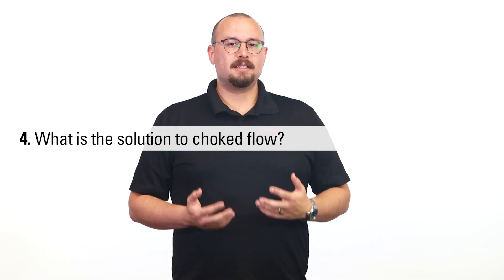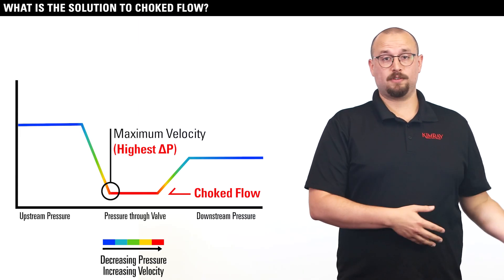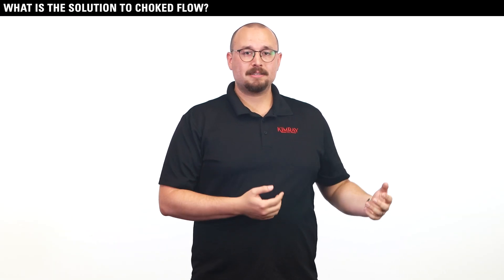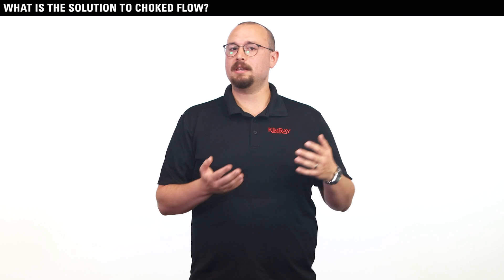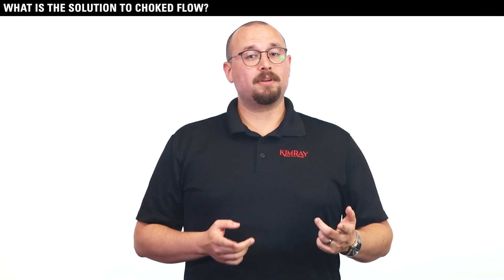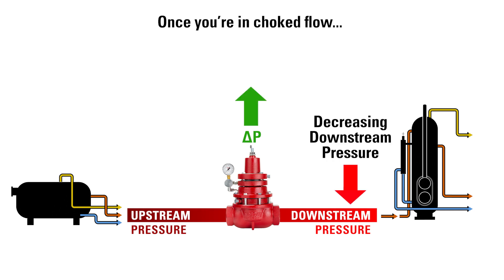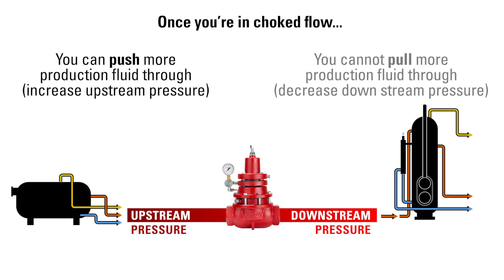Question four addresses this issue by asking: what is the solution to choked flow? To get your valve out of choked flow, you must decrease the pressure differential or increase the orifice size of the valve. If you are worried about not passing enough volume through the valve in choked flow, you need to increase your valve trim size, or you can increase your upstream pressure. One important distinction: once you're in choked flow, decreasing downstream pressure to increase the pressure differential doesn't do anything to increase the flow rate. In other words, when you're in choked flow, you can push more production fluid or gas through, but you can't pull more through.